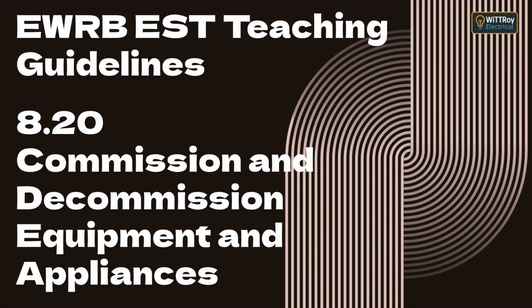2. Neutral and earth reversed. If the neutral is connected to the earth terminal, the metal body of the motor becomes energized whenever the circuit is live. Touching it could cause a severe electric shock. It also defeats RCD protection because the return path is no longer through the neutral conductor. 3. Active and earth reversed. If the active conductor is connected to the earth terminal, the entire motor frame and exposed metal parts become live at 230 volts. Any contact could be fatal, and protective devices might not operate immediately if fault impedance is high. These examples show why careful identification, polarity testing, and verification are absolutely essential before energizing.